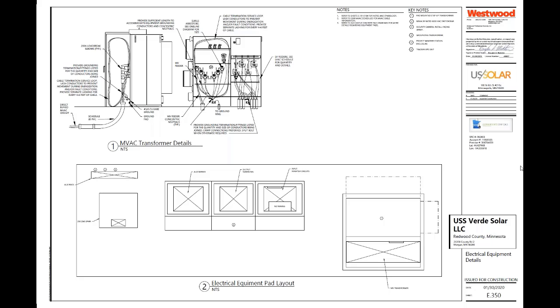And that obviously is a big play in how they are routing the conduits on a site. Are the strings flowing left, right, east, west, north, south? And so we can on a project have some switchboards that are orientated in one direction and some that are orientated in the other direction with our modular construction. Typically on that same pad, you're going to have the zigzag transformer and you're going to have an auxiliary rack where oftentimes that's where a customer is going to be mounting their metering components.